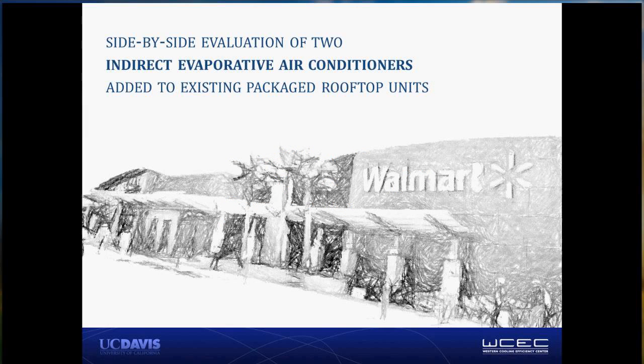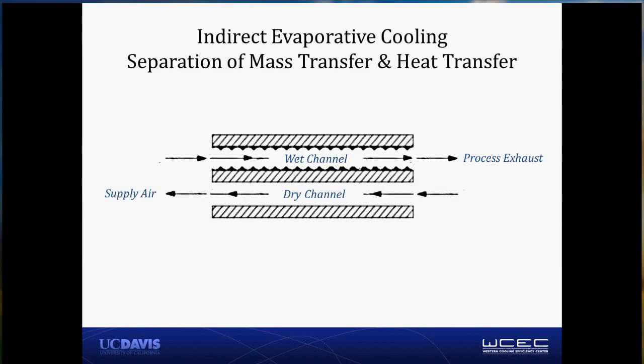So first, let's talk about this side-by-side evaluation with Walmart in Bakersfield, where we added indirect evaporative air conditioners to several existing rooftop package units. Just to review, in case not all of you are familiar with the basis of indirect evaporative cooling, the technology uses a plate heat exchanger, which is integral to the operation of the equipment. There are 2 separate airflow paths. We typically call them the primary path and the secondary path.